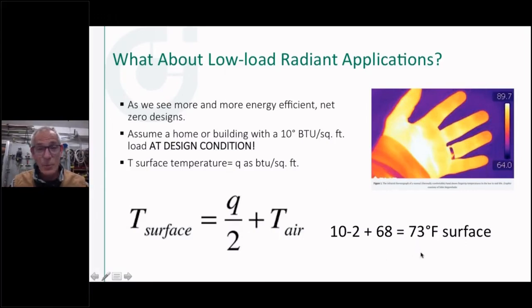If you're selling this to a customer as a warm floor house, they're going to walk in there and say, my floors actually feel cool, not warm. And you're going to say, well, what's the temperature? Well, it's 72 degrees in here. The heating system is covering the load, but it's not getting the floor warm. So there's the math to calculate that. If we know what the load is and we know the ambient air temperature, in this case I'm calling it 68 degrees, to get that 10 BTUs per square foot I only need a surface temperature of 73 degrees. Now, the good news about that is if I've got a ModCon boiler, I'm probably going to run that boiler at 80, 85 degree supply temperature. I'm going to have a great condensing condition and keep that up in the high 90% efficiencies. But you want to make sure that if the customer is expecting warm floors, that's not going to be the case.